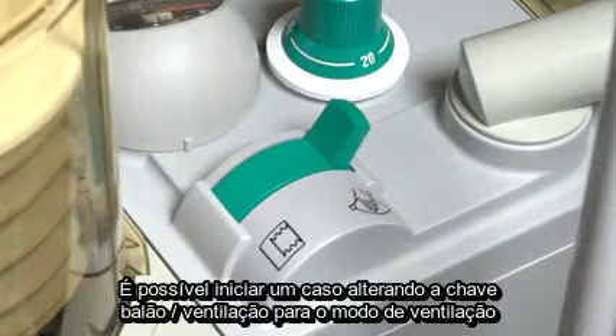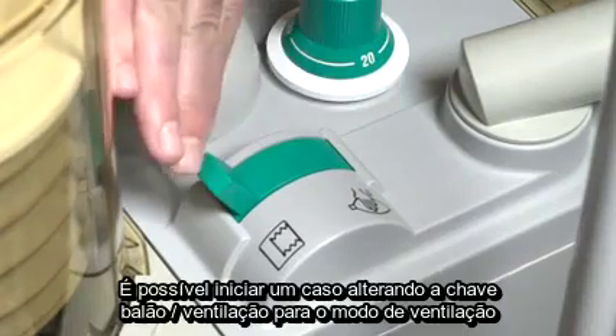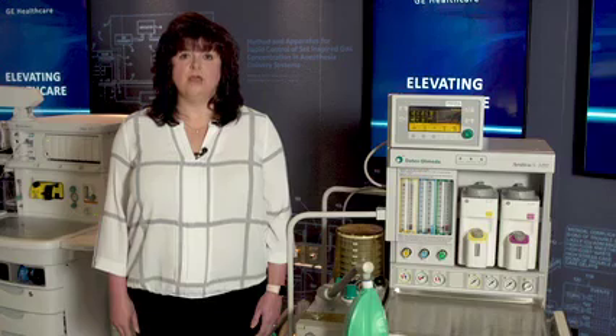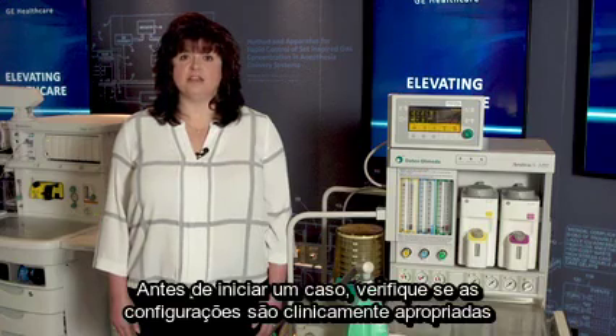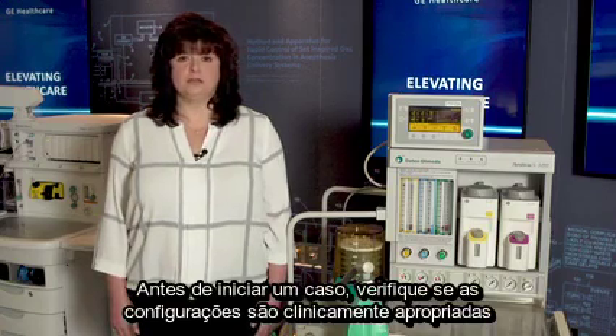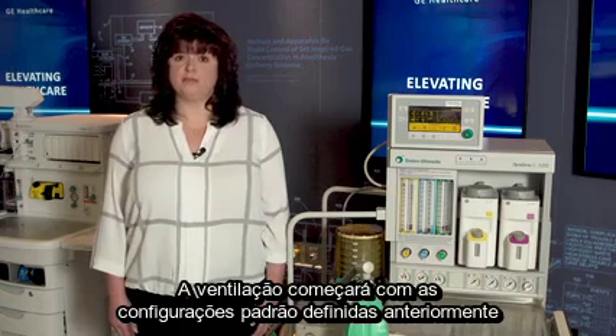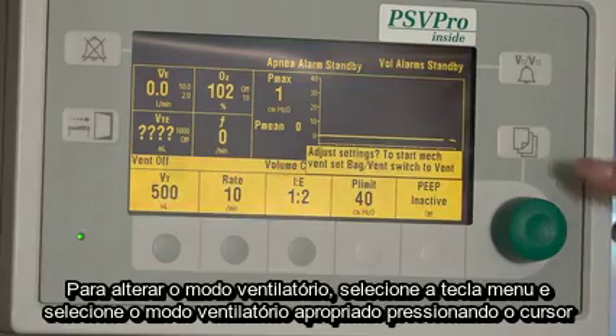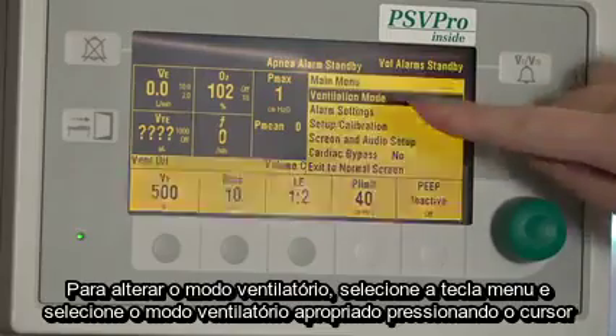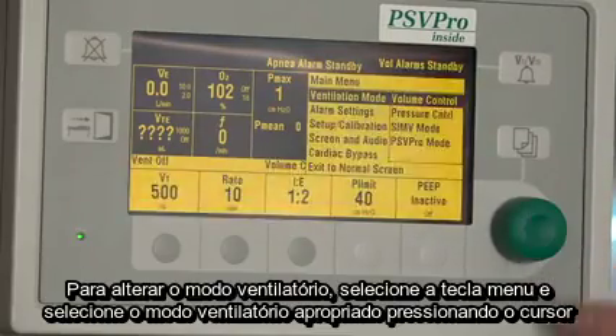A case can be started by switching the bag to vent switch to vent mode. Before starting a case, verify the settings are clinically appropriate. Ventilation will begin at the previously configured default setting. To change the vent mode, select the menu key and select the appropriate ventilation mode by pressing in the COM wheel.